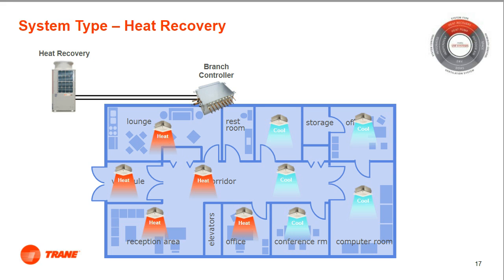heat pump outdoor units do not readily convert in the field to heat recovery outdoor units, and they require a piece of equipment referred to as a branch controller for 2-pipe systems and a heat recovery control unit for 3-pipe systems. A manufacturer's difference for heat recovery is often referred to as 2-pipe or 3-pipe systems. This describes the number of refrigerant pipes and phases of refrigerant being sent between the outdoor unit and the branch controller or heat recovery control unit. I will discuss this difference in a little more detail shortly.